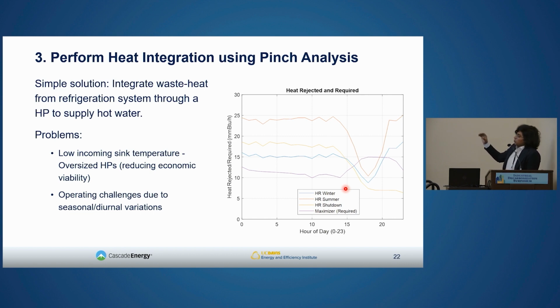Why is this a simple solution? Because we've not evaluated any heat exchange possibilities up to this point. A couple of problems, which were also highlighted by Raj earlier, with going directly to a heat pump is that you might oversize your heat pump when you don't need that heat pump capacity. And another is that you can see our heat loads, both heat rejected and heat required, are modulating or changing during the day as well as during different seasons. So trying to operate a heat pump with these changing conditions can prove to be a challenge.